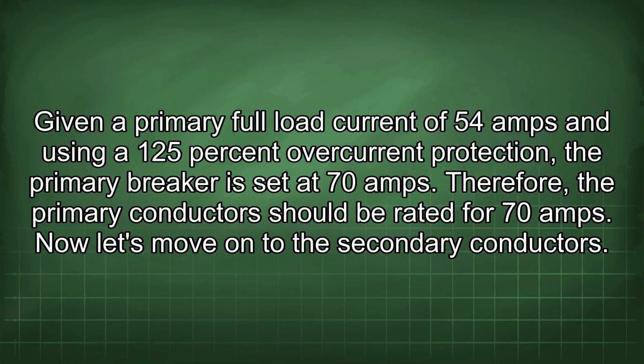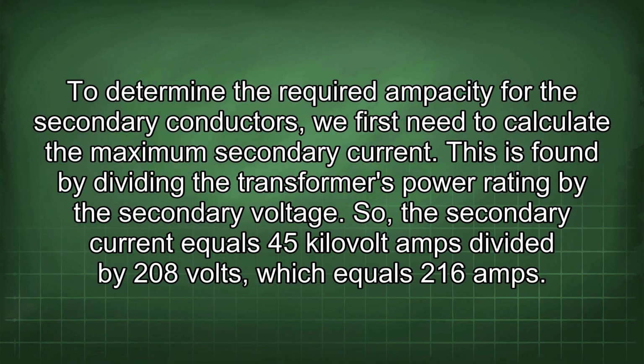Now let's move on to the secondary conductors. To determine the required ampacity for the secondary conductors, we first need to calculate the maximum secondary current. This is found by dividing the transformer's power rating by the secondary voltage. So, the secondary current equals 45 kilovolt amps divided by 208 volts, which equals 216 amps.